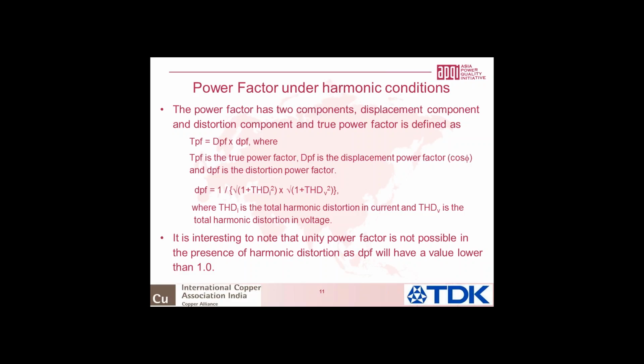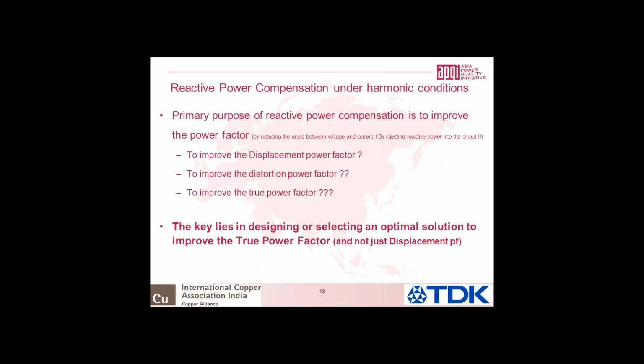Because if you have a distortion in voltage or a distortion in current, theoretically, we will never be able to achieve unity true power factor. One can still achieve unity power factor in terms of only the displacement power factor, but the distortion power factor would never be 1. It will be less than 1, maybe 0.999, but nevertheless, it will never be 1. So with this as the basic, let's look at how we do reactive power compensation under harmonic conditions. We have to re-question the fundamental stuff we agreed upon a few minutes back, that the primary purpose of reactive power compensation is to reduce the phase angle between the fundamental of voltage and current. That may not be valid anymore. The question now is, under harmonic conditions, what is the purpose of reactive power compensation? To improve the displacement power factor, to improve the distortion power factor, or to improve the true power factor?